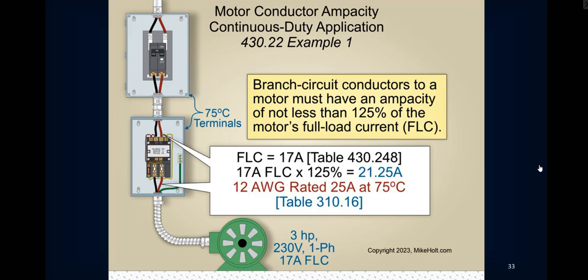So, the FLC, first of all, the FLC is in the NEC. I would write that down. The full load current is what you are sizing. Overcurrent protection, ground fault, and short circuit protection is sized based on the FLC. Now, there's some caveats to that, but that's the essentials of it. Also, branch circuit conductors to a motor must have an ampacity of not less than 125%. That means when you're calculating the motor overcurrent protection and you're in the conductor sizing, you're going to take that ampacity and multiply it by 125%. We have some other factors involved here, but that's the baseline.